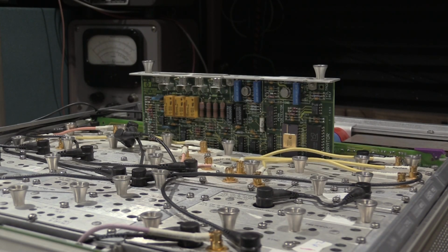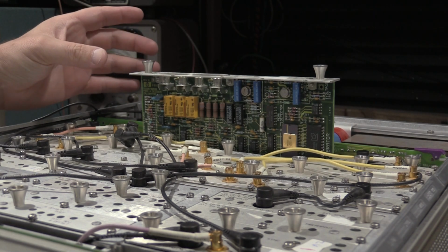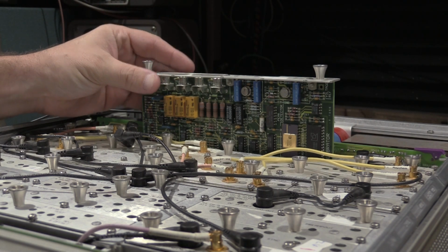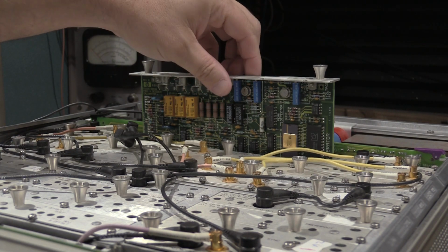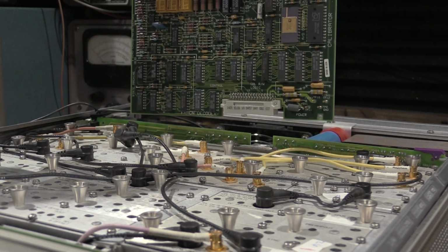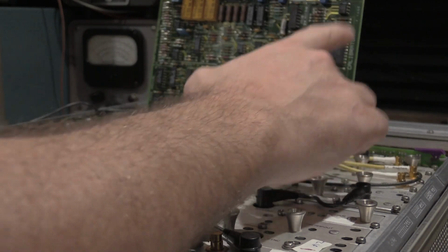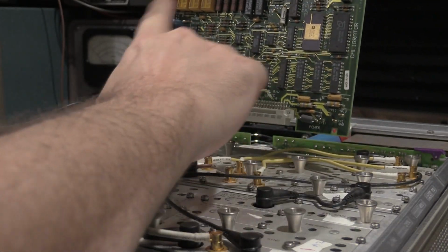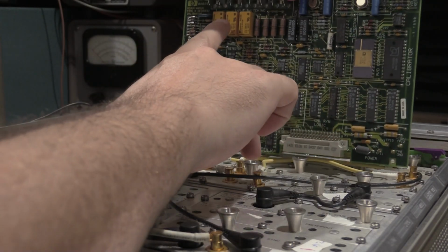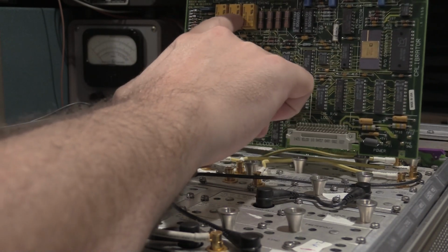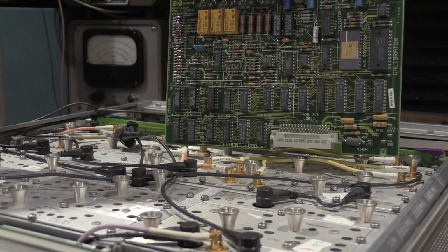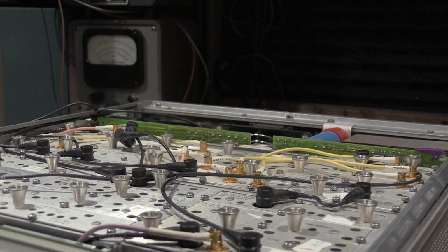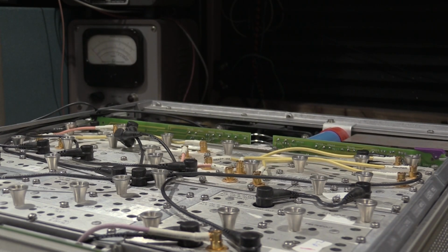Okay, in an effort to find this DC offset problem, I pulled out the A36 board, which has the calibrator, the reference, and a bunch of other stuff on it. So we have the calibrator section, references up here, and we have some analog input switching right here, and I am very curious about these relays. Some of these relays are known to be a problem, so let's take a look at those on the DMM.